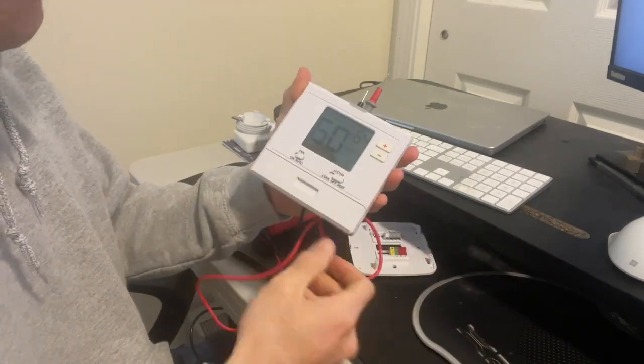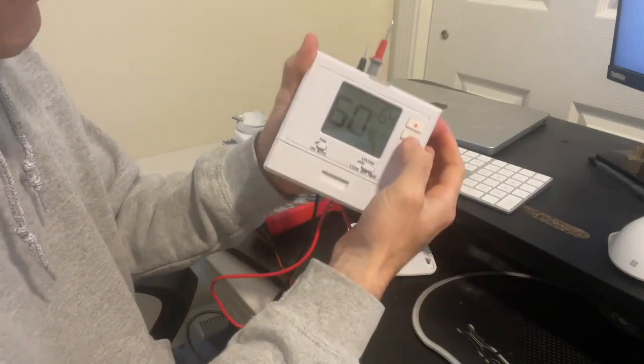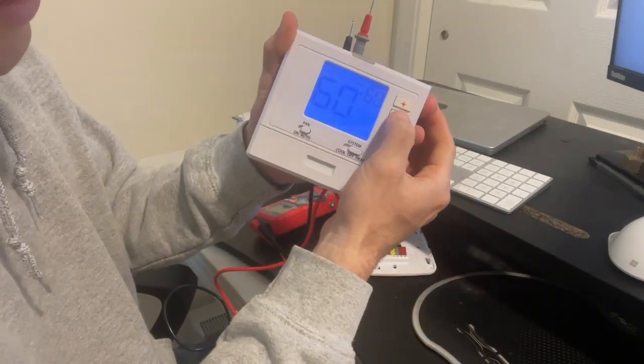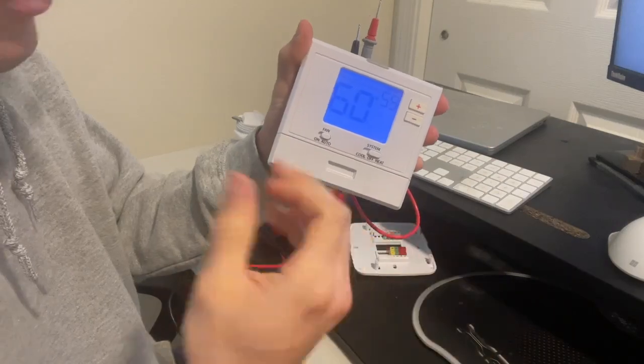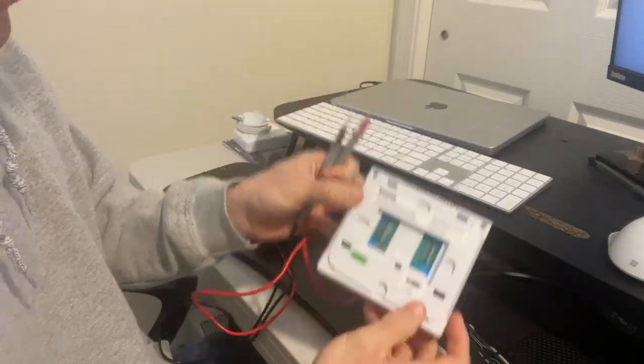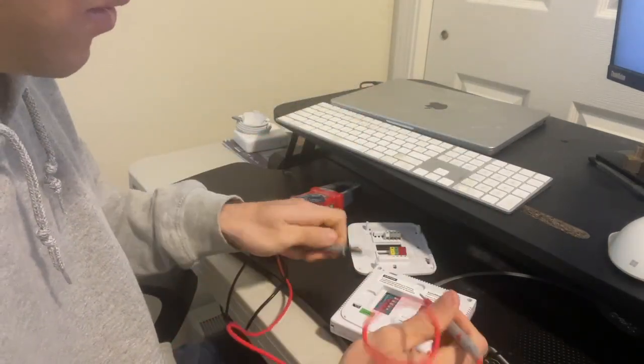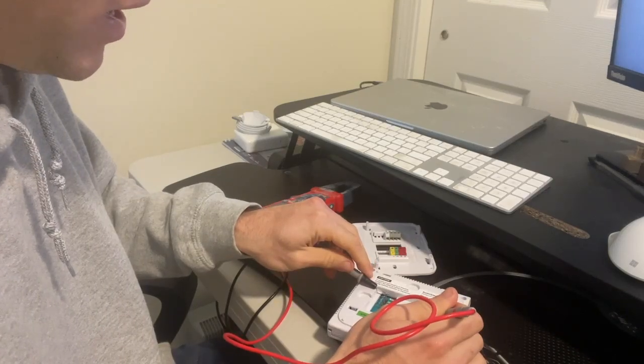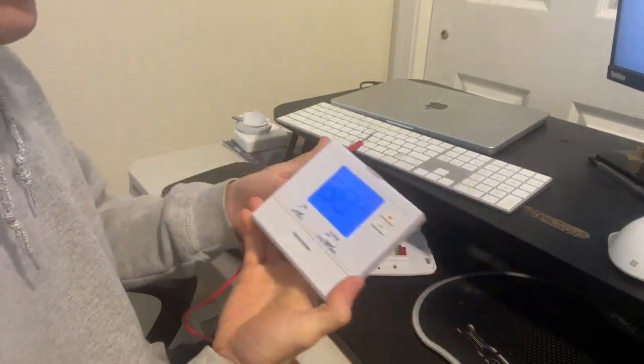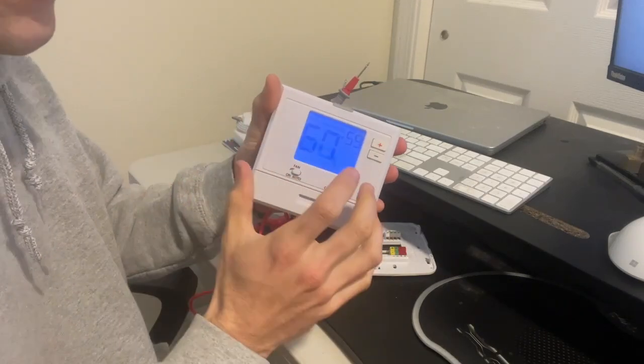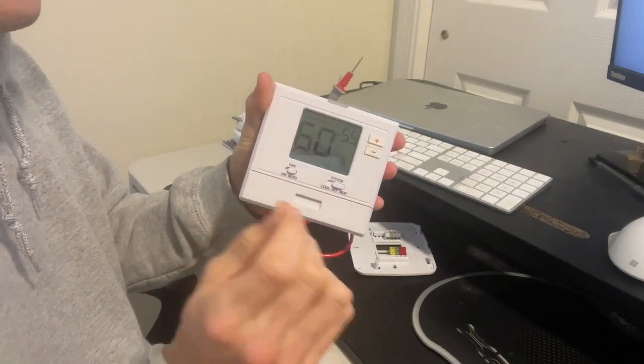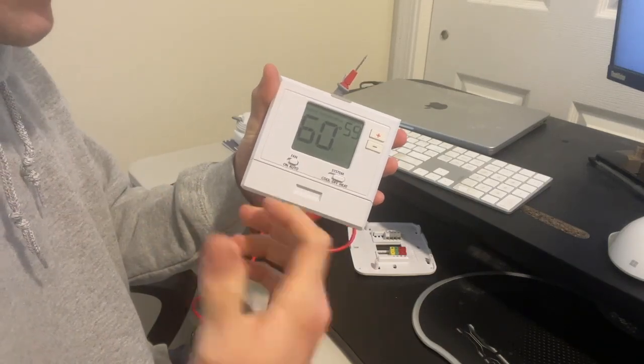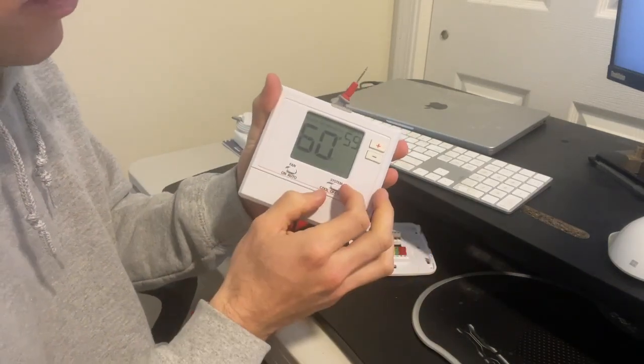And just to confirm that when I'm not heating my house, if I lower my set point temperature to like 59, again, we heard the tick. So it stopped that connection. And we go back to here. I'm going to check between RH and W. And I'm not hearing anything right now. So that tells us that the thermostat is correctly connecting the wires to get your furnace to kick on during the heating of your house.